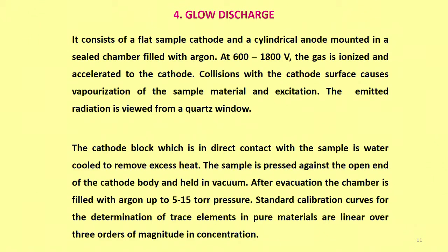So, after evacuation the chamber is filled up again with argon gas at 5 to 15 torr pressure. What is torr? Torr is a unit of pressure, a fraction of an atmosphere. Then you should make a calibration curve as usual for the determination of trace elements in pure elements, just like what you do in spectrophotometry etc. Plot the emission versus concentration and make the reading. Unknown also should be referred to that.